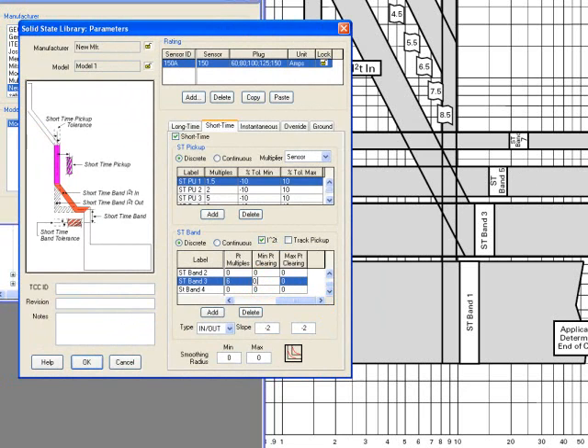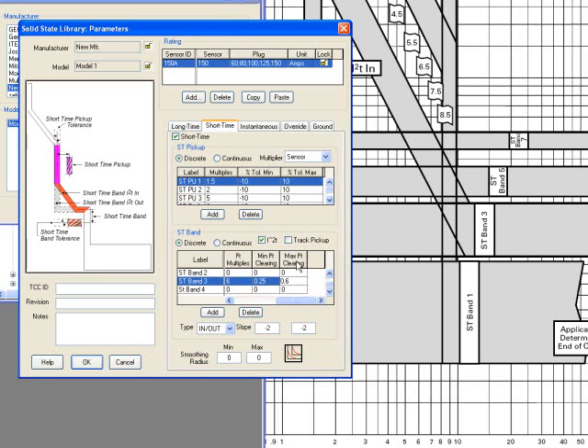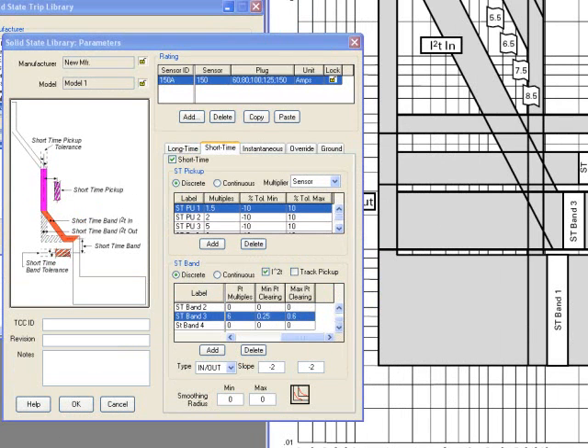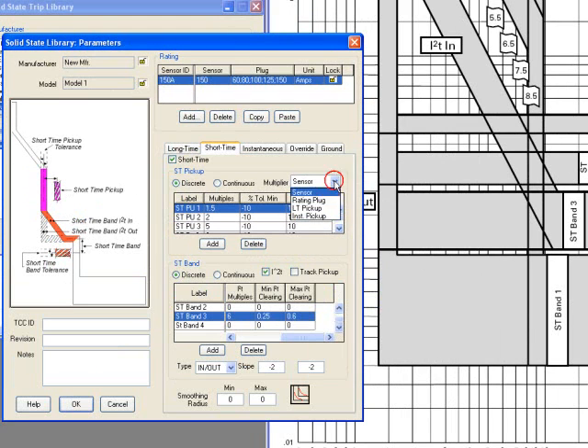So by specifying these two numbers, you can have a slope shape for a Short Time band. If you check this box as a track pickup, the Short Time band will keep tracking based on the Short Time pickup. Whatever you set as a Short Time pickup is going to be your Short Time band. Make sure you select the right multiplier for your Short Time pickup.